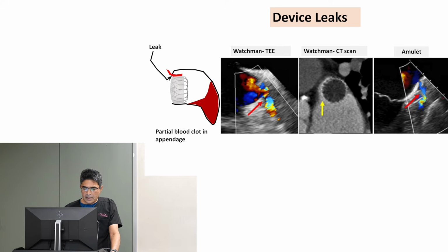So when you have a device that is not properly deployed, you can have a leak. In this pouch, the blood can flow in and out, carrying blood clots from inside to the outside, causing stroke. So you can see a leak that is shown on an ultrasound. This is color Doppler that's showing the leak. This is a CAT scan that is showing a leak. This is a color Doppler showing a leak in an Amulet.